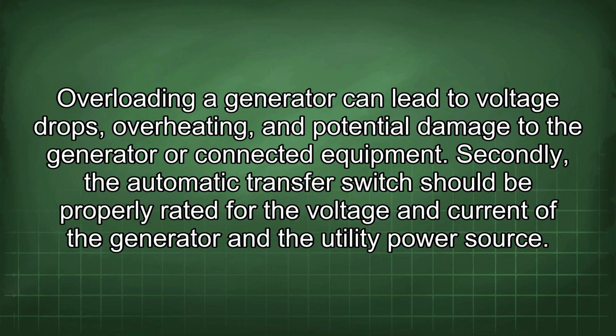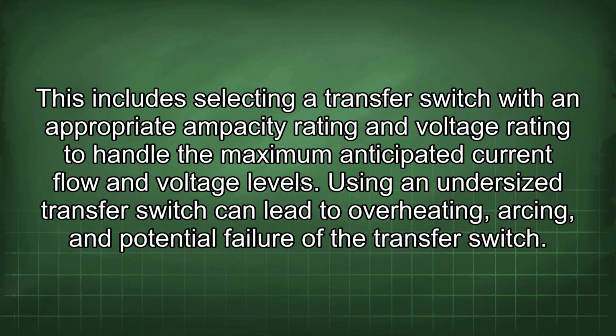Secondly, the automatic transfer switch should be properly rated for the voltage and current of the generator and the utility power source. This includes selecting a transfer switch with an appropriate ampacity rating and voltage rating to handle the maximum anticipated current flow and voltage levels. Using an undersized transfer switch can lead to overheating, arcing, and potential failure of the transfer switch.